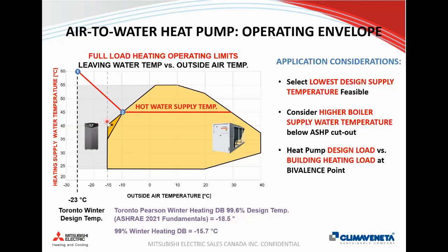So it's going to be interesting to see what technology is out there over the next couple of years. But even working with this type of heat pump that gives you low grade heat at colder temperatures, as long as you design it properly in the system, you can still leverage that to ensure that you're taking full usability of the heat pump.